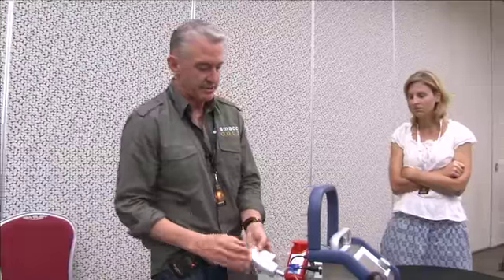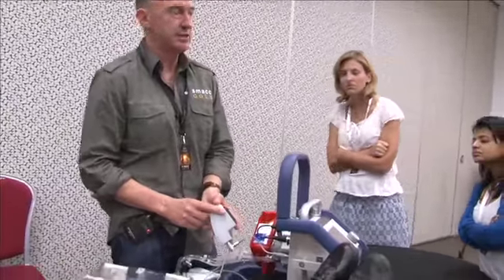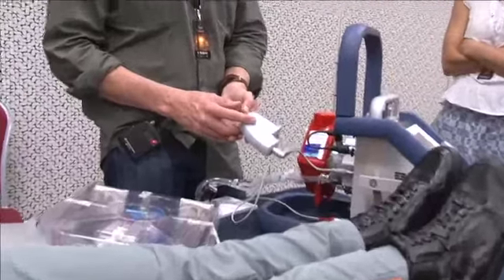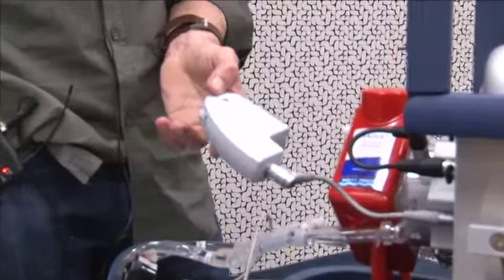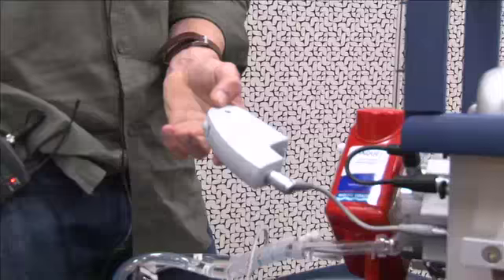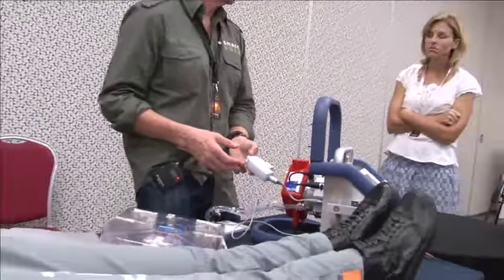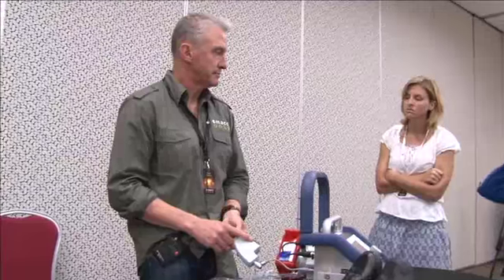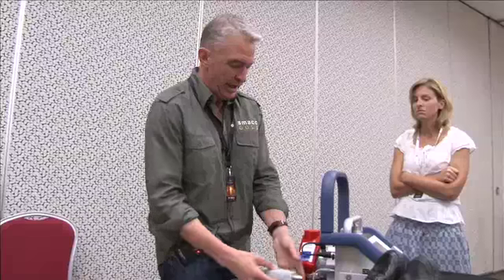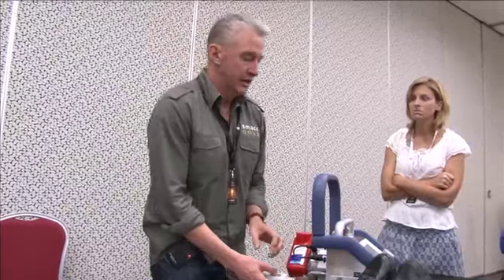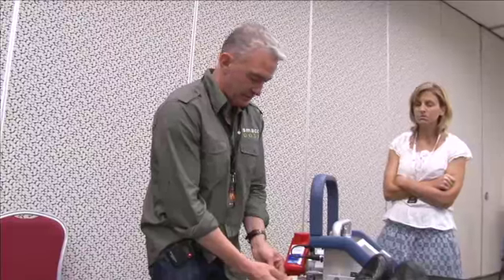The other sensor this has, which is very useful clinically, is this sensor here, which measures the saturation in the venous line. So it's analogous to mixed venous oxygen saturation. So it's a useful sort of global marker for the patient's perfusion state. And this also has an inbuilt hemoglobin or hematocrit sensor as well. So you get continuous hematocrit, continuous mixed venous oxygen saturation, internal pressures, temperature, it gives you the temperature of the patient as well, and all that with a battery backup, which is good usually for at least an hour or so on this pump.